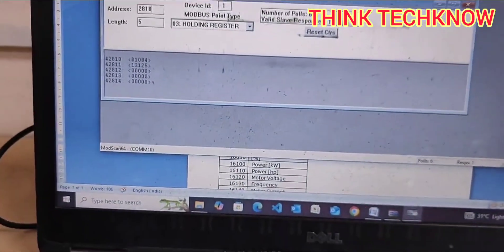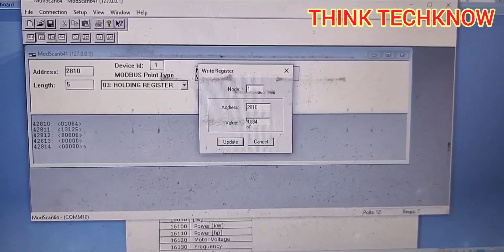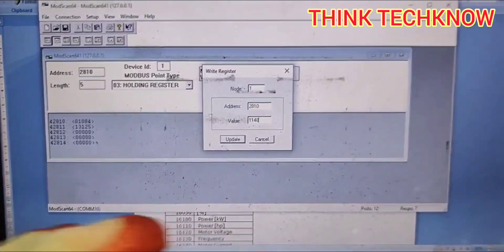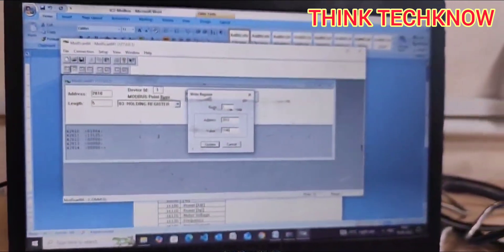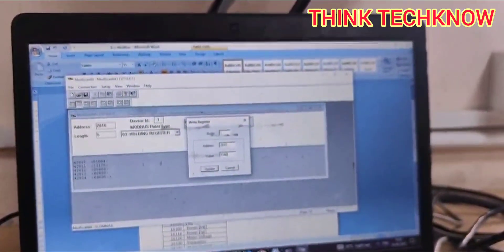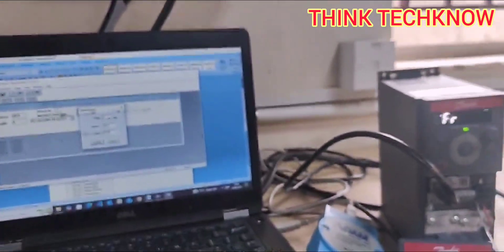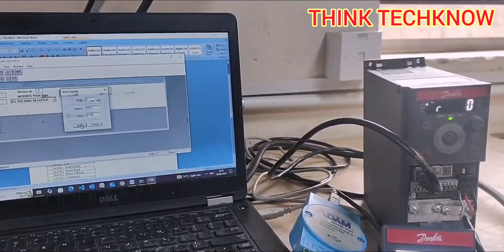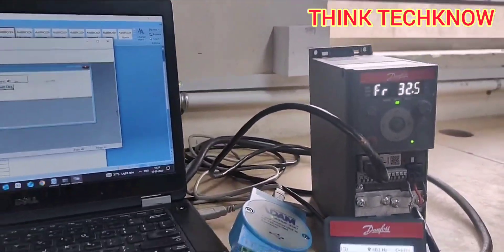Now I am entering the values for start address 2810. Now we get the slave response. 2810 is for start and stop command. Inside 2810, there are two sub addresses: 1148 for start and 1084 for stop. Now I am fixing the value 1148 here. I am giving update. You can see the drive is running now.